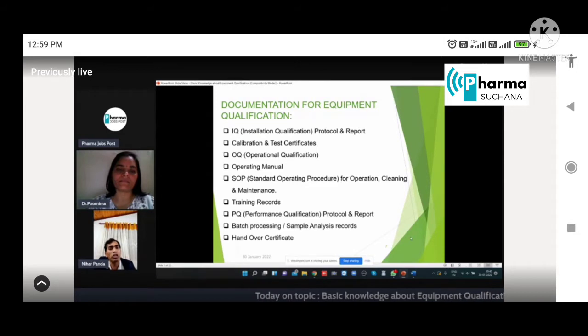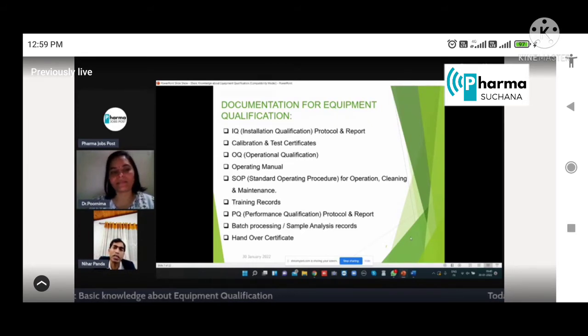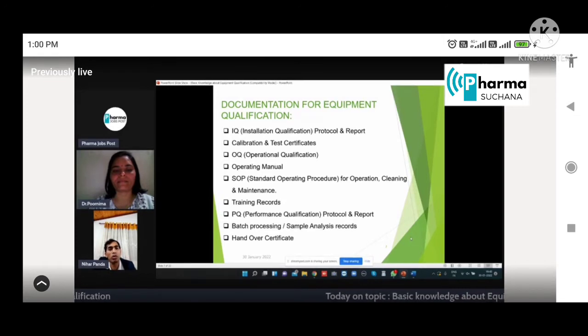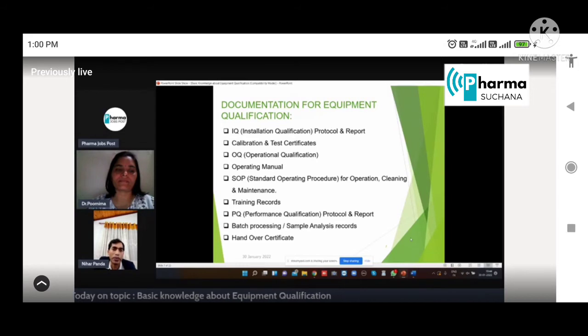IQ document, IQ protocol and report. The IQ protocol can be prepared by the manufacturer who is providing the equipment or by the user also. If the vendor is not providing the IQ document, then the user can prepare the IQ document based on the URS and DQ. After completion of the protocol, the protocol should be signed, approved. Then the IQ should be executed. This time either the service engineer or the site engineer can execute the IQ part.